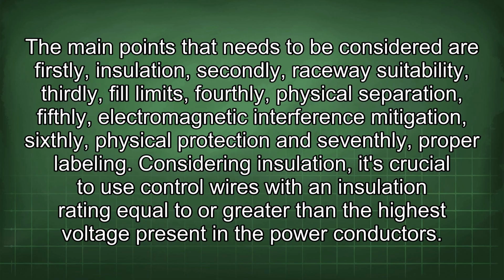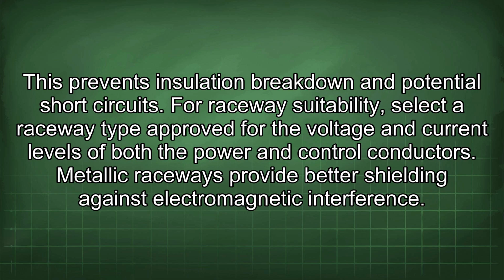Considering insulation, it's crucial to use control wires with an insulation rating equal to or greater than the highest voltage present in the power conductors. This prevents insulation breakdown and potential short circuits. For raceway suitability, select a raceway type approved for the voltage and current levels of both the power and control conductors. Metallic raceways provide better shielding against electromagnetic interference.